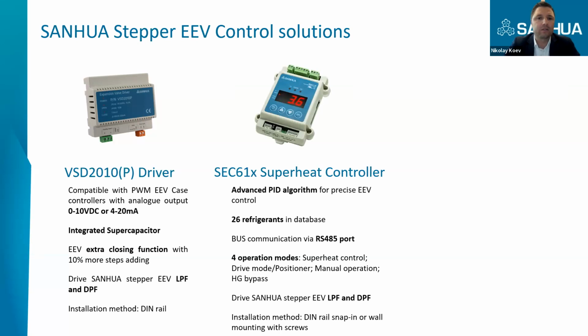Another very interesting and, I would say, elegant solution is for customers who want to upgrade their systems from simple thermostatic expansion valves and solenoid valves to electronic expansion valves, but also want to keep the same control configuration, let's say simple thermostat case controllers, which usually measure the temperature and control the solenoid valve. Here we offer our superheat controller, which can be integrated very easily with thermostat case controllers, just receiving a run signal and running or stopping the valve.